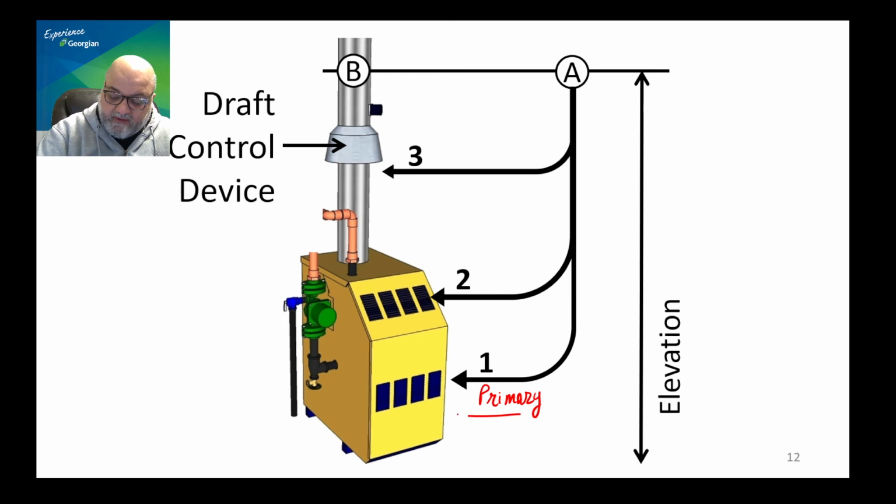because supposedly this air is going to be mixed with the gas prior to the combustion, and we can call this secondary air because it will surround the flame and provide oxygen to particles of the fuel gas that are not yet burnt but are exposed to the ignition temperature, and they can burn in the presence of oxygen.